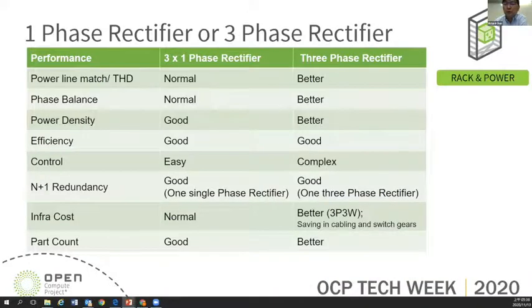So furthermore, we made a table to compare these two kinds of solutions. To check the power balance and the input THD, we think the 3-phase can get good results. And since we have a lower part count for the 3-phase, I think the power density and part count for the 3-phase are better than the single phase. I think the only thing is that the control of 3-phase is complicated. However, we have some UPS and heavy DC power designs, so the 3-phase topology is very familiar to our team, and also to the industry. So we can leverage some of that to do the 3-phase design.